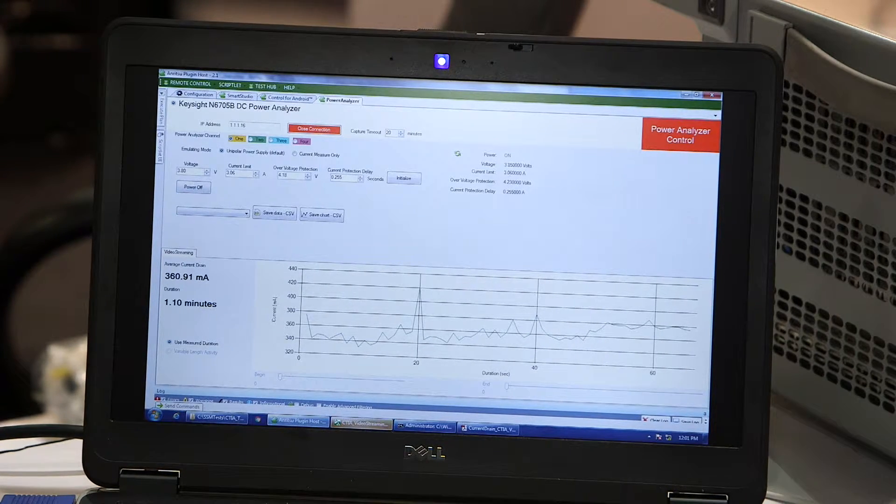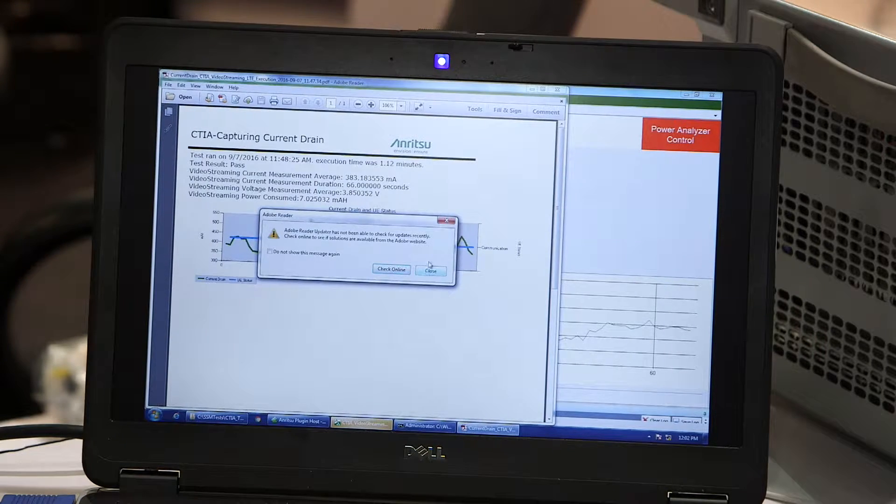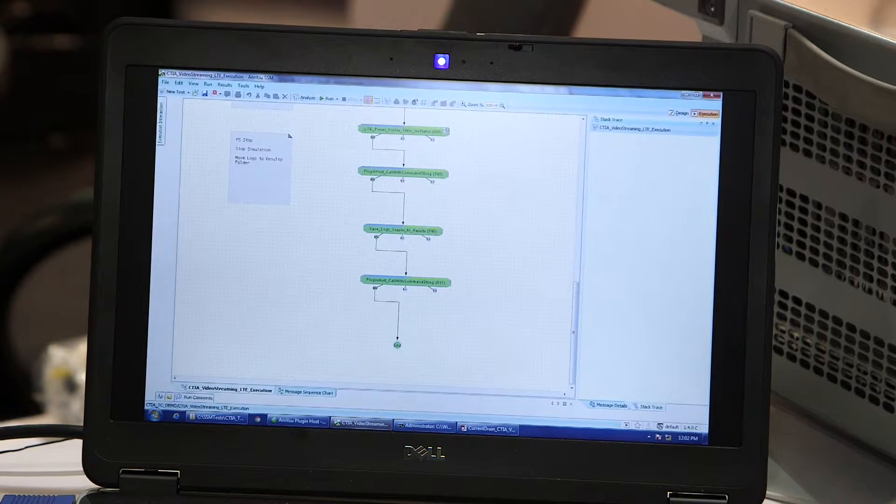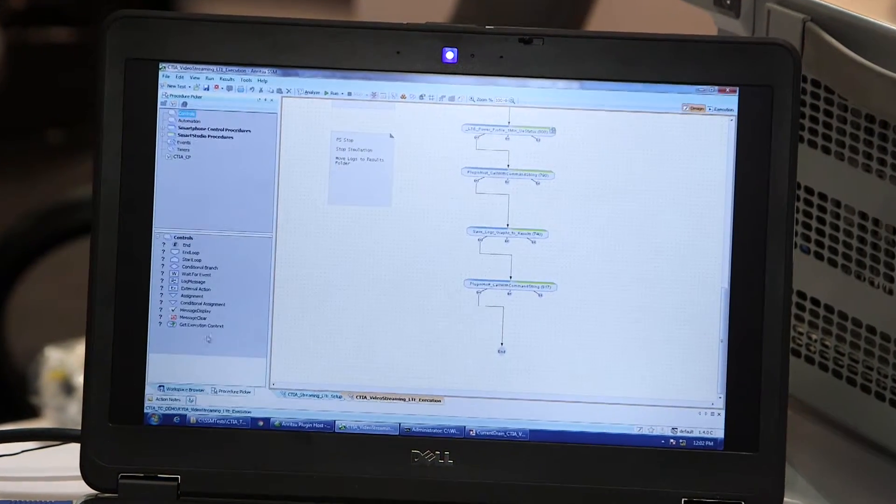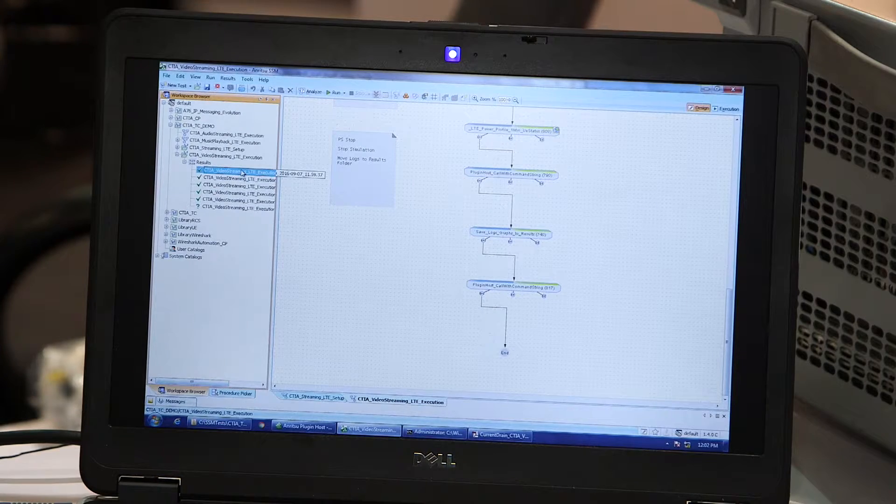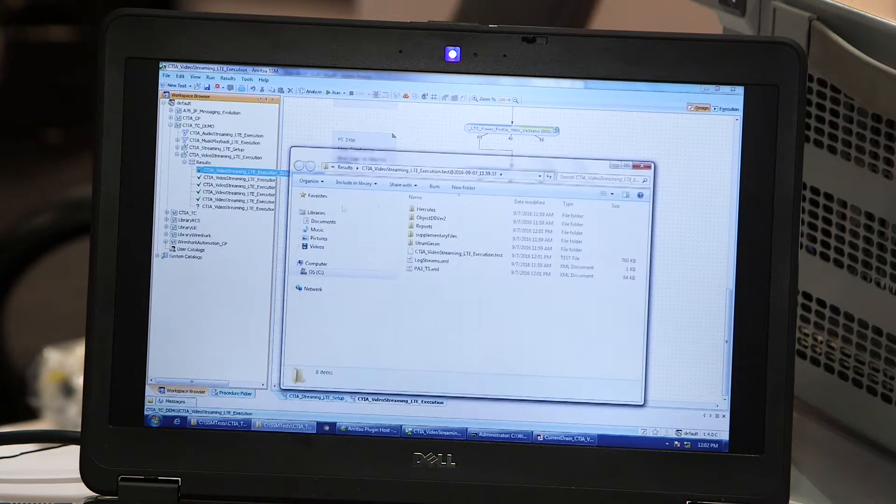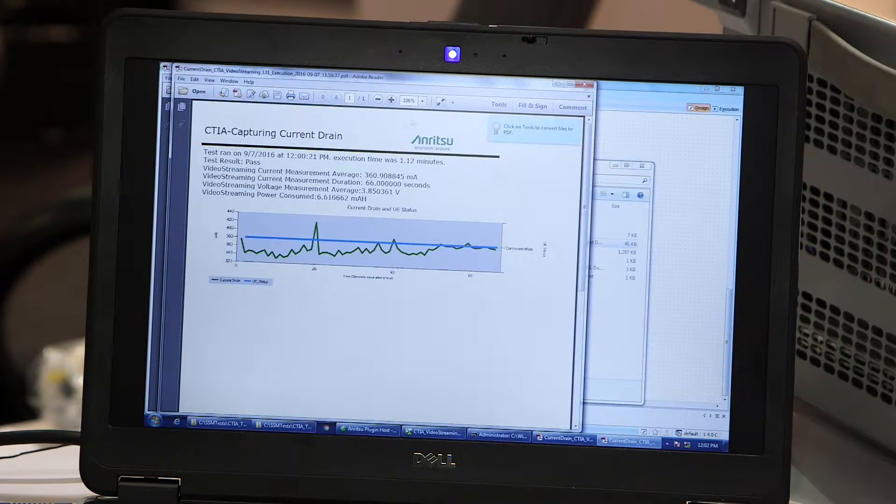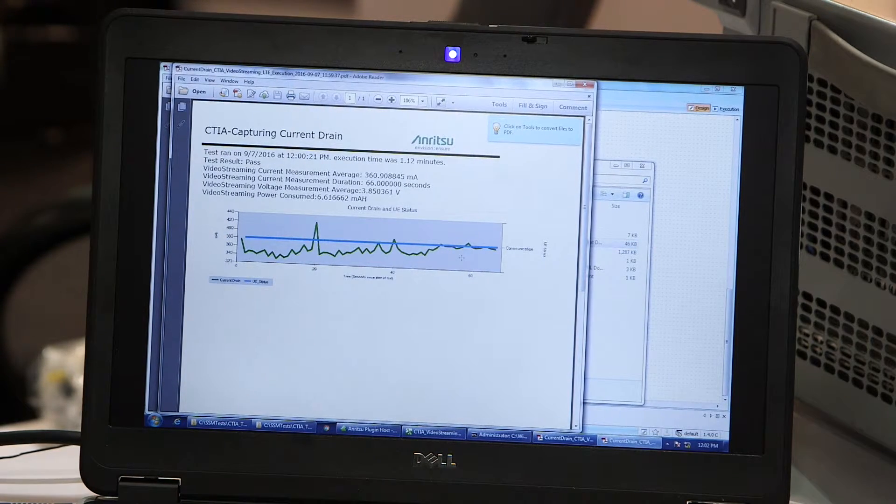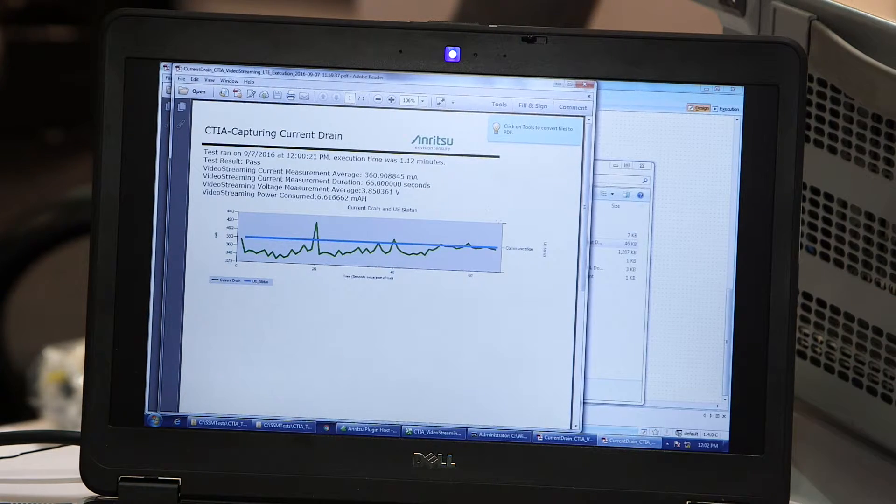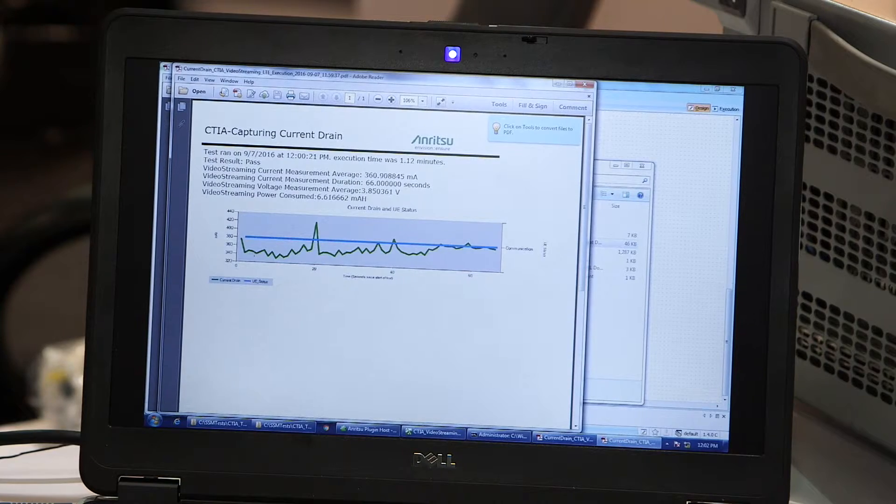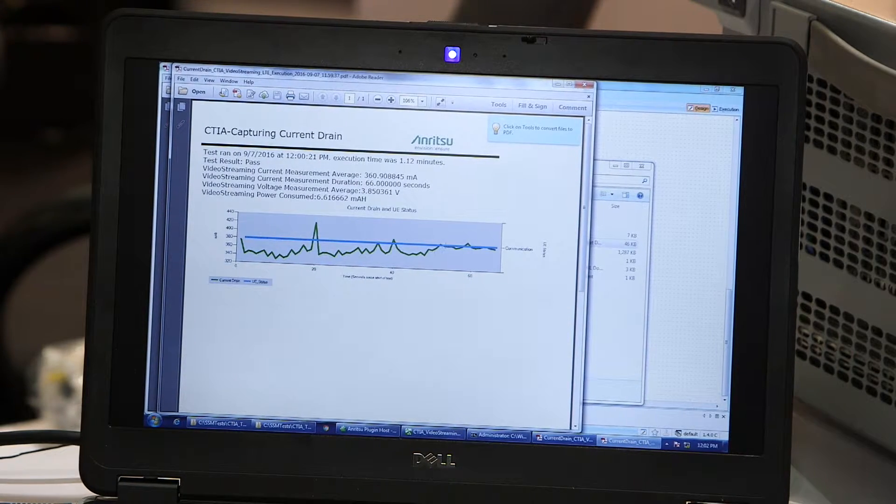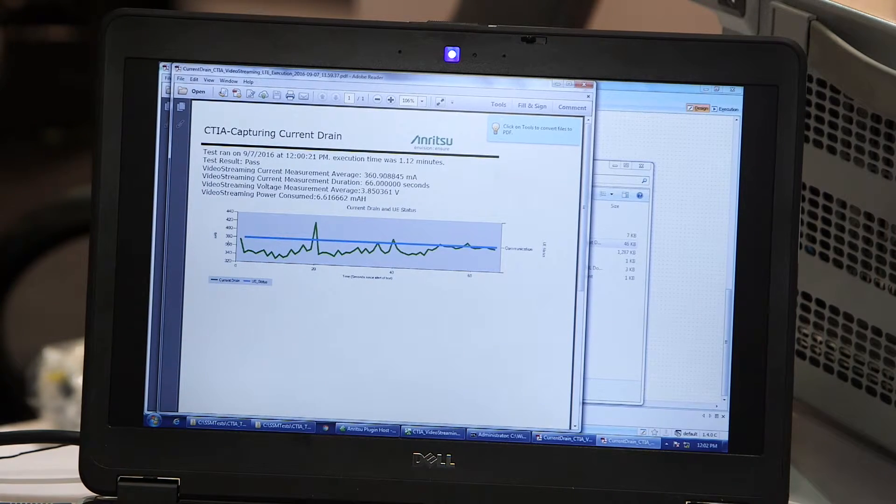All the results can be viewed, the reports can be viewed from this control PC. This is the test case that we just ran. You can see the duration, you can see the average current drawn. You can also see we started with the low uplink power from minus 20 dBm all the way to 24 dBm. You can see that the current drawn has gone from 340 all the way to like 380 milliamps.